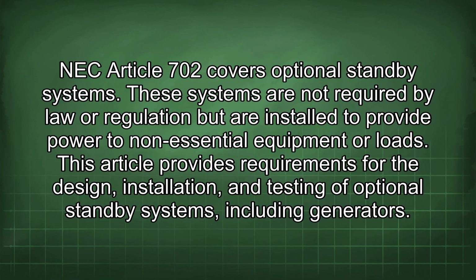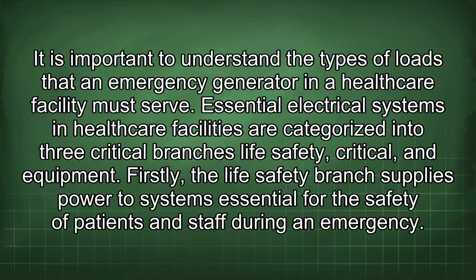NEC Article 702 covers optional standby systems. These systems are not required by law or regulation, but are installed to provide power to non-essential equipment or loads. This article provides requirements for the design, installation, and testing of optional standby systems, including generators. It is important to understand the types of loads that an emergency generator in a healthcare facility must serve.